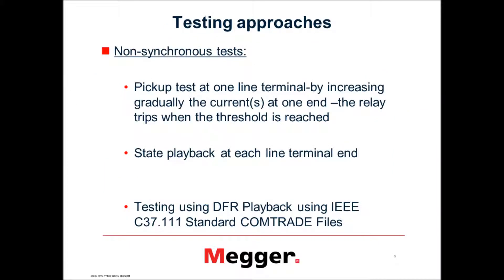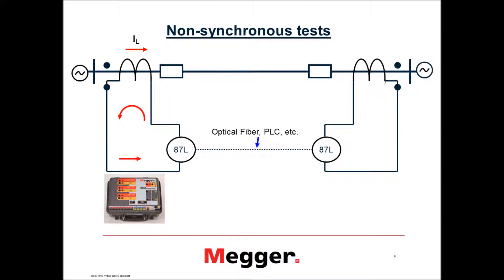For testing approaches, we have non-synchronous tests where you would take a test system, do a pickup test on one end of the line by increasing the current and monitoring when the system trips. You could also do a state playback where you apply a pre-fault and a fault and then time it. You can even play back a digital fault recording from a digital fault recorder in the IEEE C37.111 standard. However, these approaches really don't test the whole system.